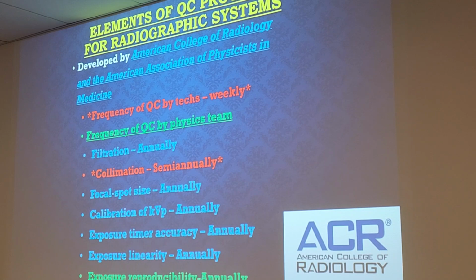Alright, so the next step, the ACR, which is the American College of Radiology, and the American Association of Physicists in Medicine, they determine the frequency in which QC testing should be done. It has up here weekly for techs. Now that everything is digital, it is probably going to be like every 2 to 3 months if it's the calibration test. If you're the QC tech, you may have some tests that you need to do, not every week, but more frequently than the calibration test. Weekly QC now mainly refers to mammo, of course, because there are weekly tests in mammo that you have to do.